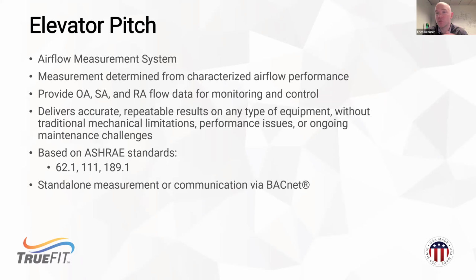And you'll see as we go through that, the best way I could describe it is that we've automated a balancer inside that flow station. So the same calculations that he would do are the same calculations that we're providing in real time. So all of this data that we're going to show you, measurements of supply, outdoor, and return, as well as all the temperatures and pressures that are required, are available via BACnet, so they can be integrated into anybody's building management system.